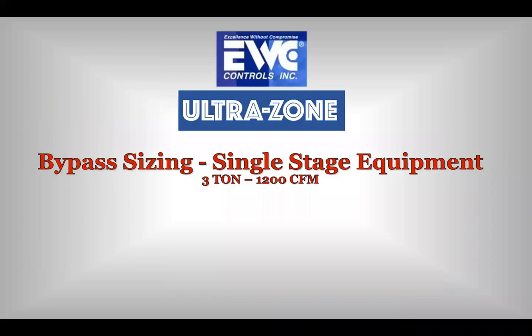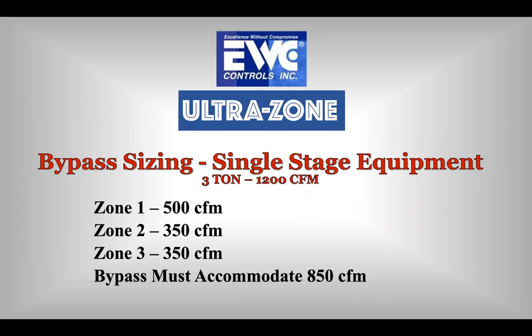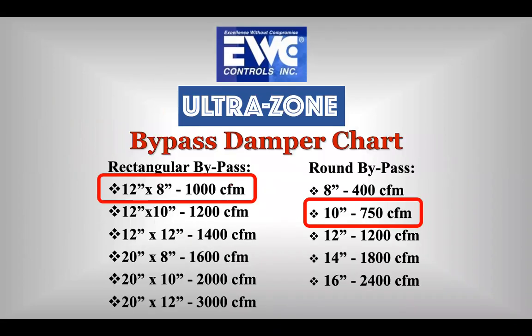Same 3-ton, 1200 CFM system, single stage. I have to go with worst case scenario. I'll account for the remaining CFM in worst case scenario, which is smallest zone calling. That means 850 CFM has to be accounted for. Go to my bypass charts. I can cover it with my rectangular.